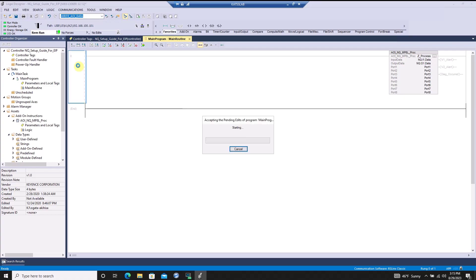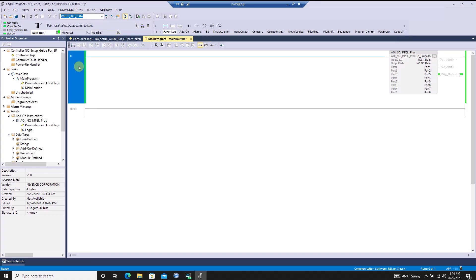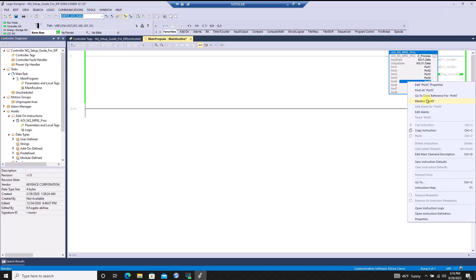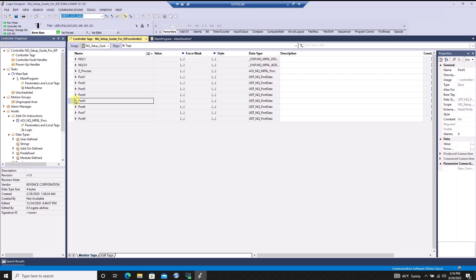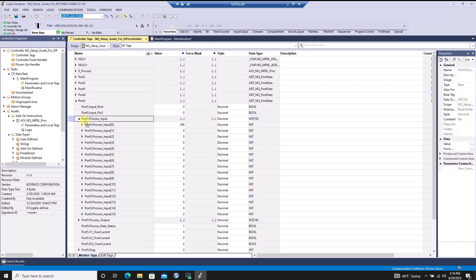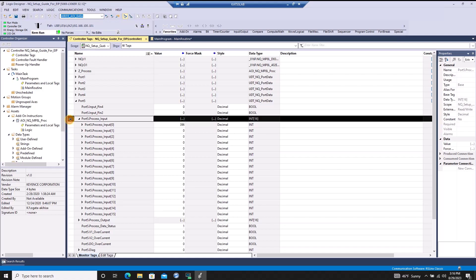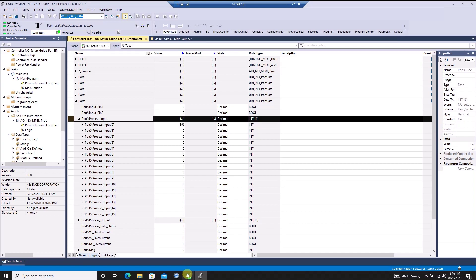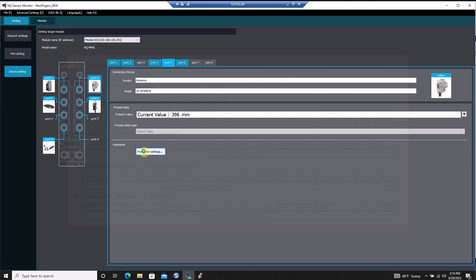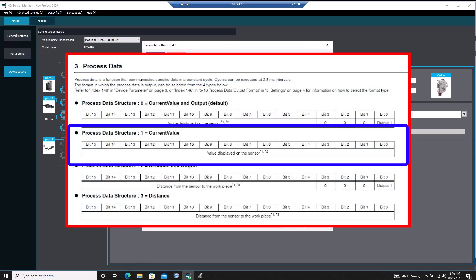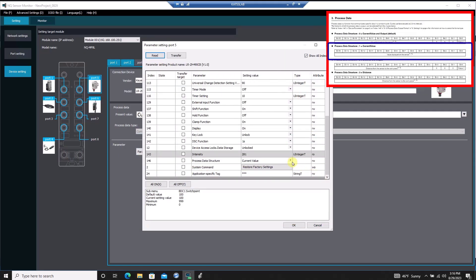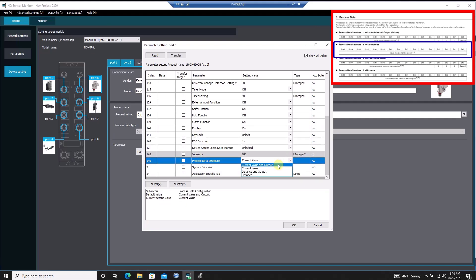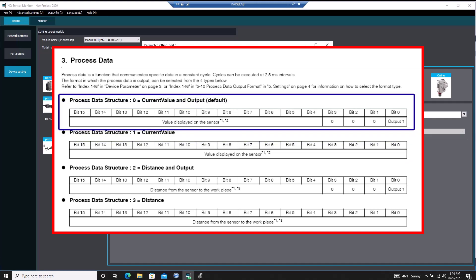Now that I'm done making tags, I'll go online and monitor port 5's data, which is where the LRZ is connected, and I'll make sure the value in the PLC's input data tag matches the value in the NQ software. Now is a good time to note that if a sensor's process data completely occupies a whole integer, like the LRZ's current process data structure, we will not need to move any bits around for the information to make sense. However, there are situations where the data only occupies part of an integer, in which case I'll need to move those bits around into their own separate integer for the information to make sense.